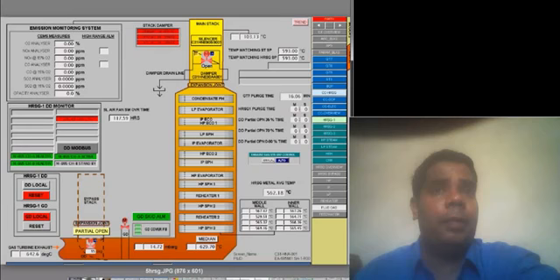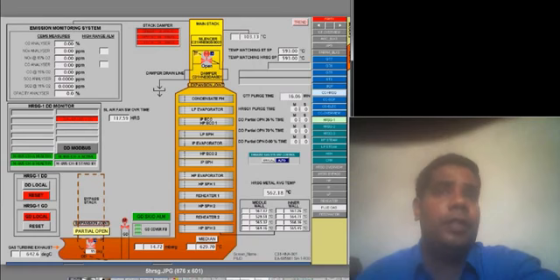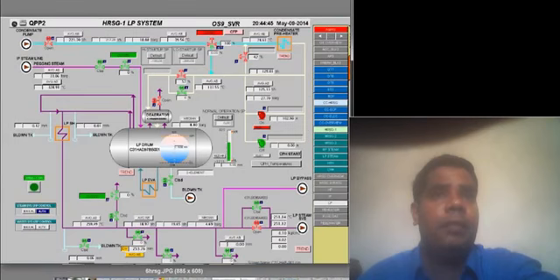And generator type was D11 type with 355 MVA and 18 kV. It is hydrogen cooled. HRSG was vertical type and triple pressure, and manufacturer was Doosan. It consists of HP, IP and LP with a diverter damper on top of LP, a guillotine damper and a stack damper. Closing speed of 60 seconds and emergency closing speed of 20 seconds. HRSG exhaust temperature was 100 degrees with 3 BFP pumps.